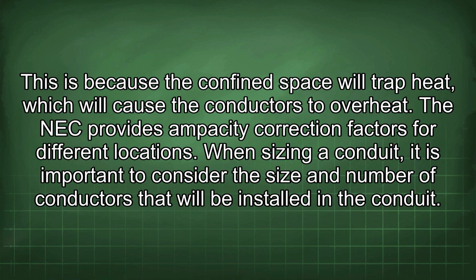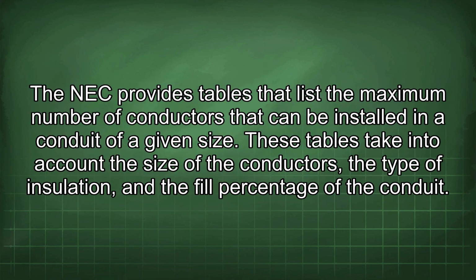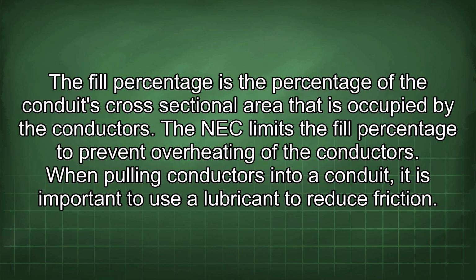When sizing a conduit, it is important to consider the size and number of conductors that will be installed in the conduit. The NEC provides tables that list the maximum number of conductors that can be installed in a conduit of a given size. These tables take into account the size of the conductors, the type of insulation, and the fill percentage of the conduit. The fill percentage is the percentage of the conduit's cross-sectional area that is occupied by the conductors. The NEC limits the fill percentage to prevent overheating of the conductors.